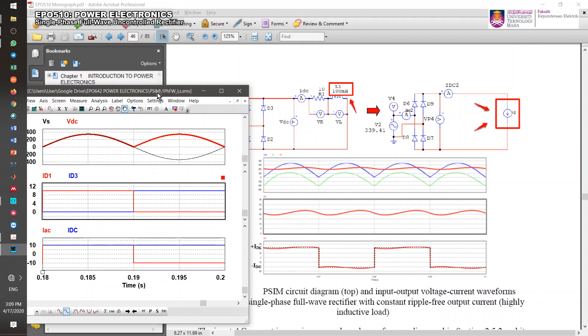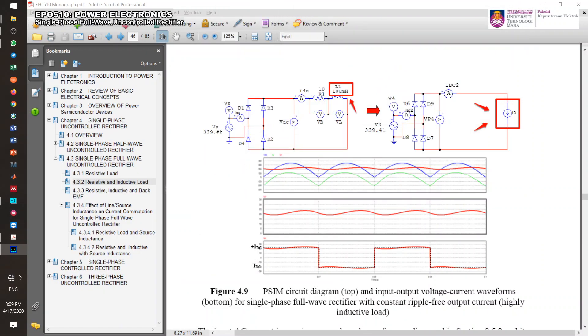Now we're going to look at what happens if there is a source inductance Ls in the front end. This source inductance may come from the cable or from a transformer, because in practical systems you have a three-phase supply from the TNB which steps down to single-phase 240 volts. Because the transformer has large windings, it is represented by a source inductance. In practice, we always have this source inductance.